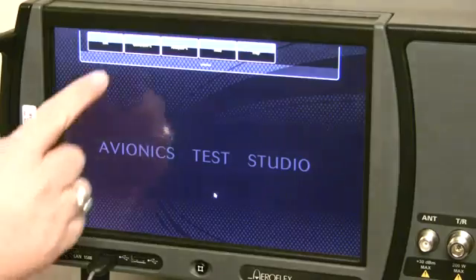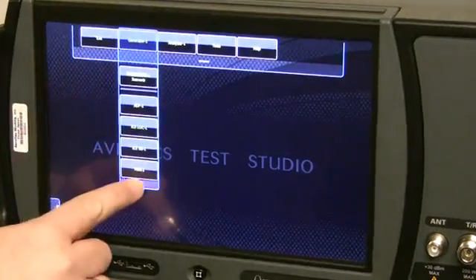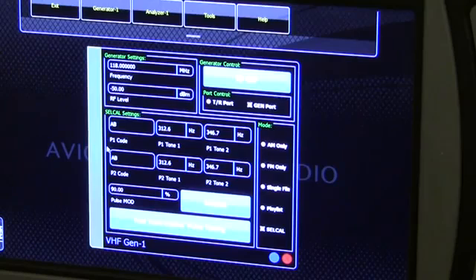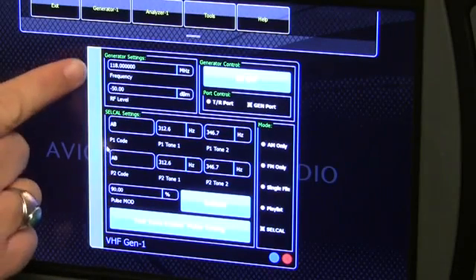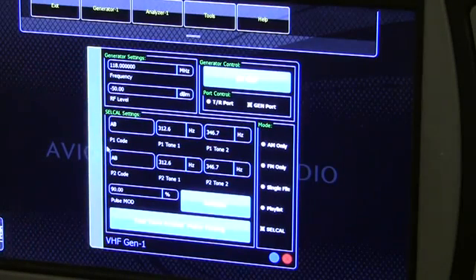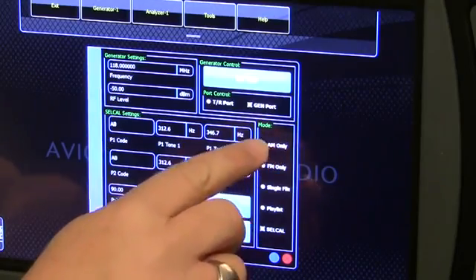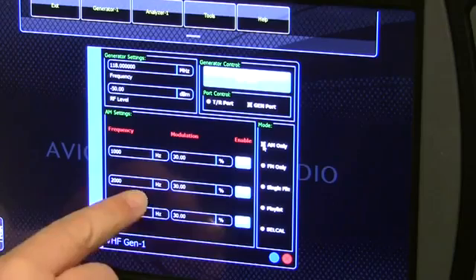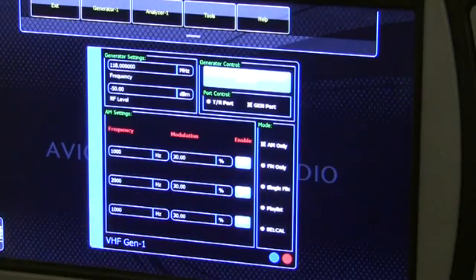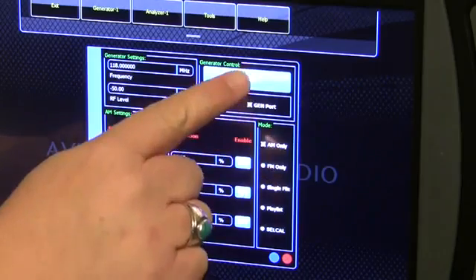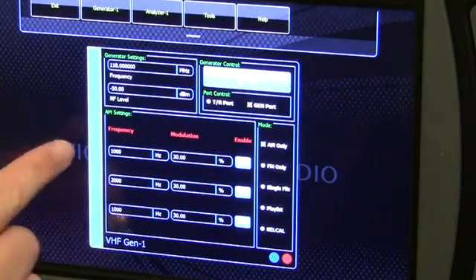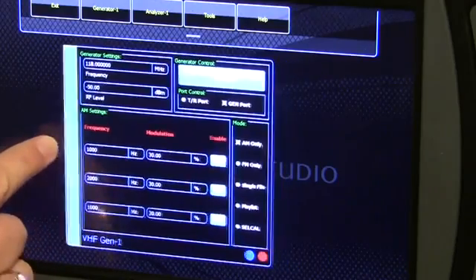Let's set up a VHF signal to loop back to the analyzer to discuss the analyzer controls. The selections we made before are still in place. Let's add some modulation by turning on the 2000 Hz at 30 percent. Ensure the port control is on GenPort and turn on the generator control. Let's now drag the VHF Gen1 screen out of the way.